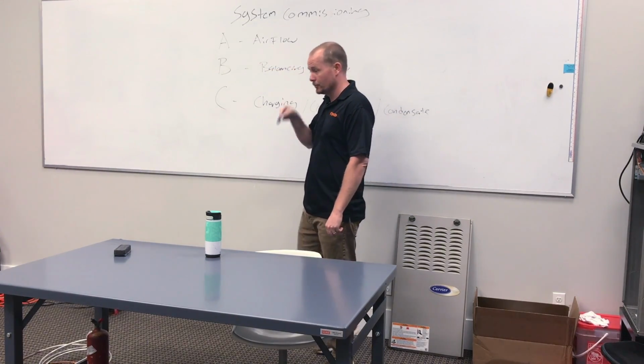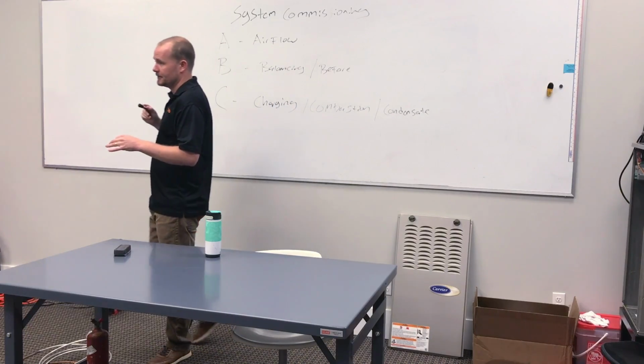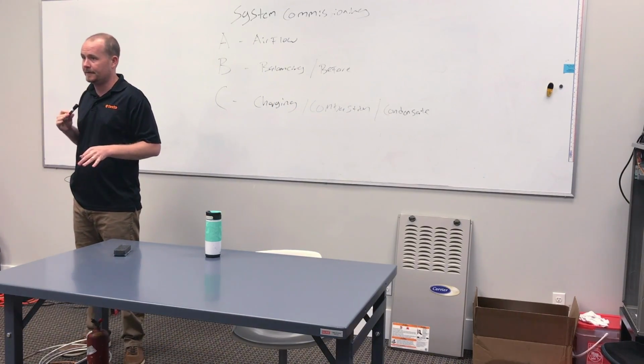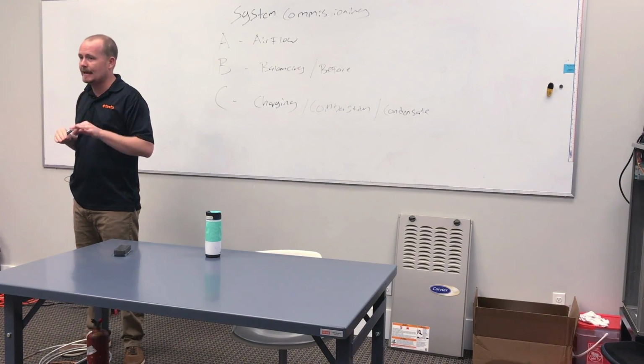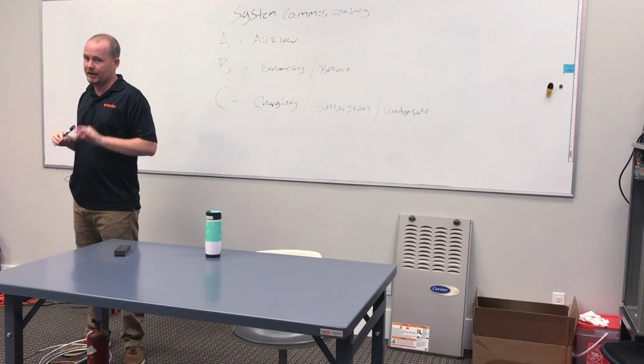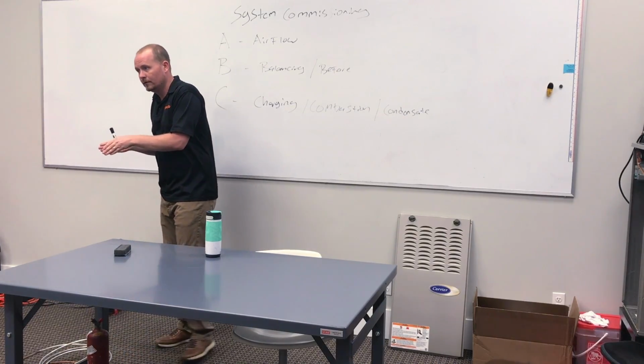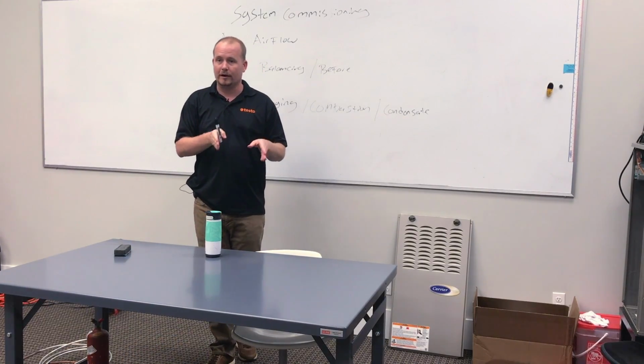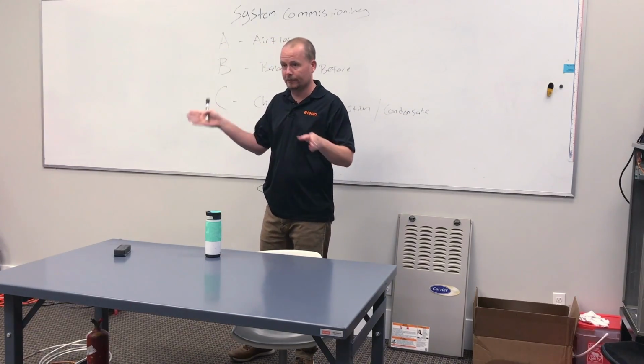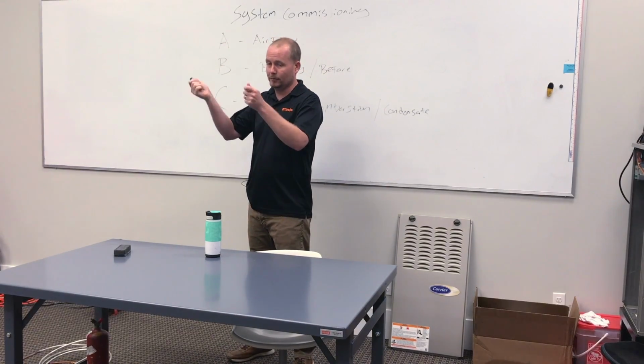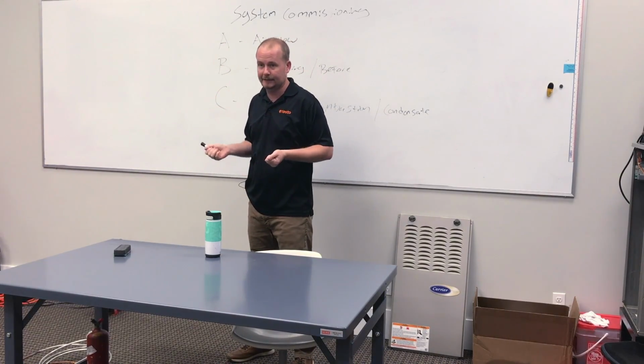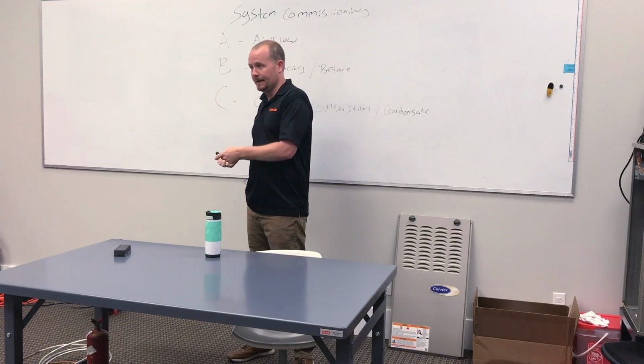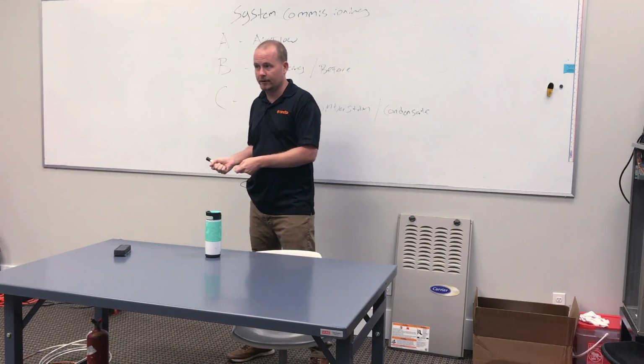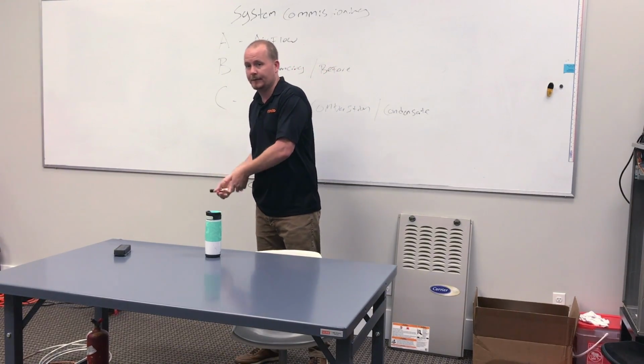And I want to talk about this real quick because I've seen this come up a few times, and I just want to make sure I'm really clear with everybody. Anytime we do any ductwork, any duct changes, we test before and we test after, and that requires the use of an airflow hood. We have several airflow hoods at Kalos. We have a couple of the little CPS guys. We got a couple of the bigger ones, right? Anytime you're changing ductwork, we have to test before and we have to test after.